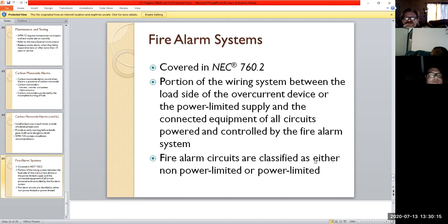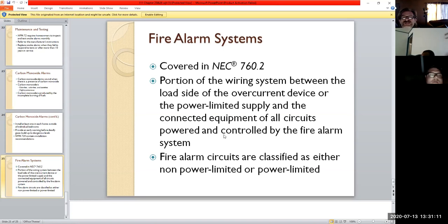So fire alarm circuits can either be classified as non-power limited or power limited, depending on the type it is. You would have to go back and see the equipment that you're dealing with here and what you paid for and that type of thing. But yeah, it's controlled by the fire alarm system. Like I say, it'd be like a central brain that controls the whole system, and it's all wired as one unit coming back. So they would have their own leg, right? They'd have their own overcurrent device, and they are required to be wired a certain way. Everything from the load side, the hot side, if you will, can connect and control and go all the way up through and feed that brain system, if you will.